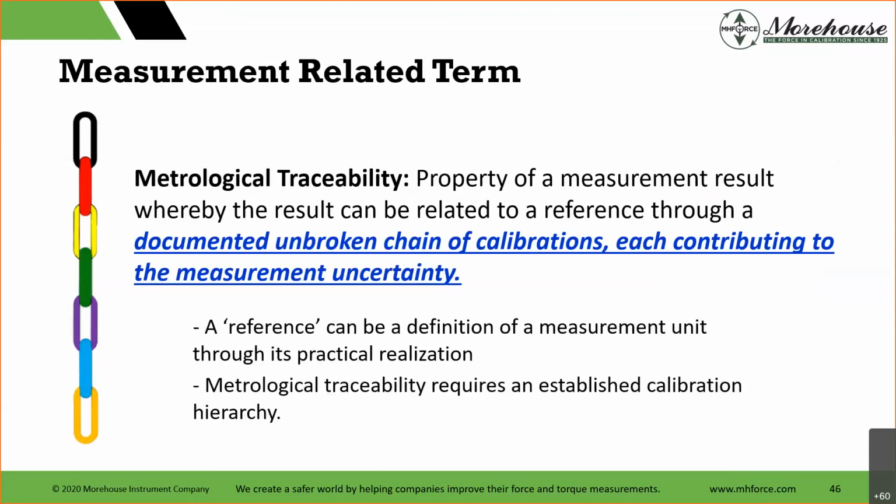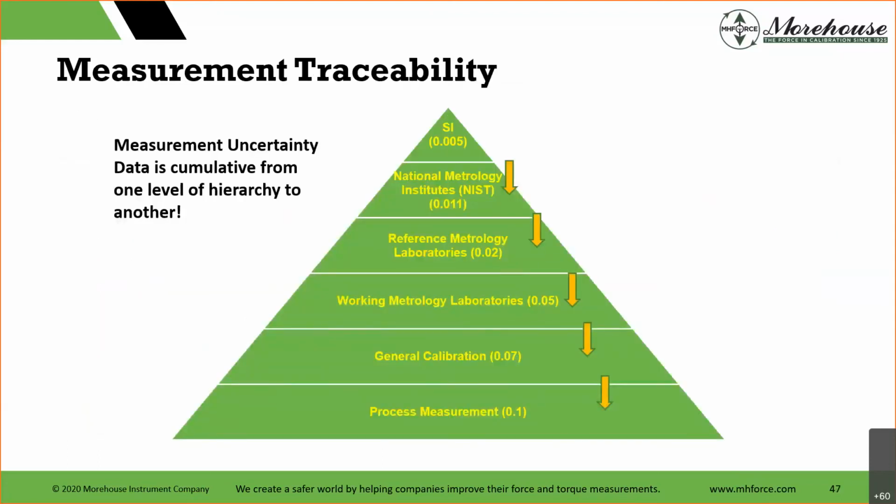We're basically saying we have an established calibration hierarchy, and it looks something like this, right? Where we have SI units defined probably at the BIPM, and then the kilogram just went, before it was an actual artifact where NIST had kilograms, they sent them to the BIPM, and they'd all be compared against each other, and then they knew it was losing some weight and other things.